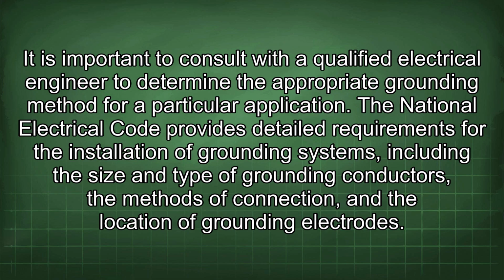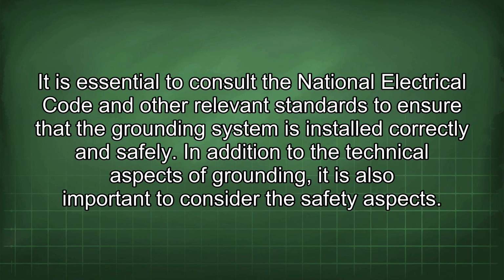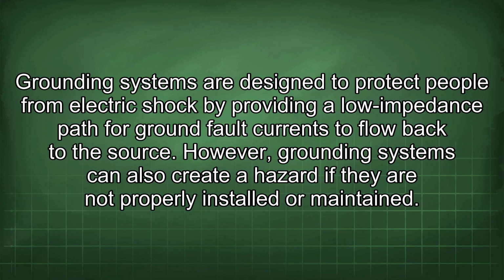The National Electrical Code provides detailed requirements for the installation of grounding systems, including the size and type of grounding conductors, the methods of connection, and the location of grounding electrodes. It is essential to consult the National Electrical Code and other relevant standards to ensure that the grounding system is installed correctly and safely. In addition to the technical aspects of grounding, it is also important to consider the safety aspects. Grounding systems are designed to protect people from electric shock by providing a low impedance path for ground fault currents to flow back to the source.